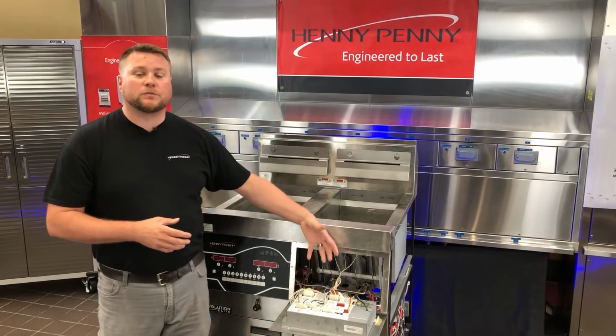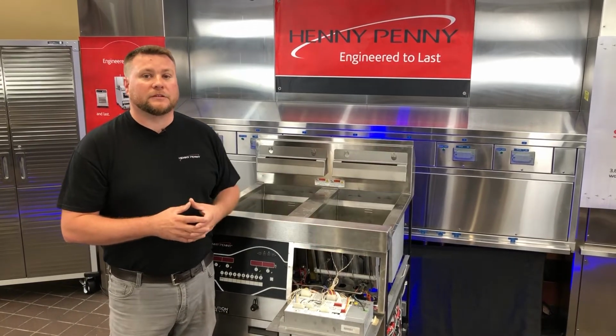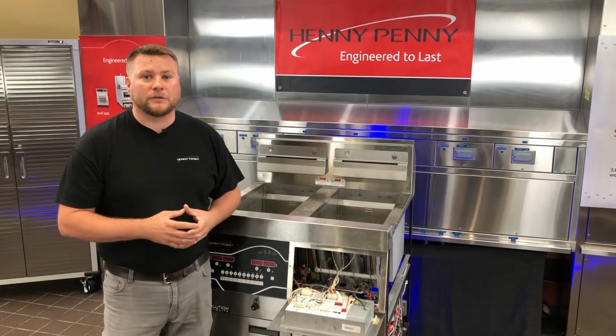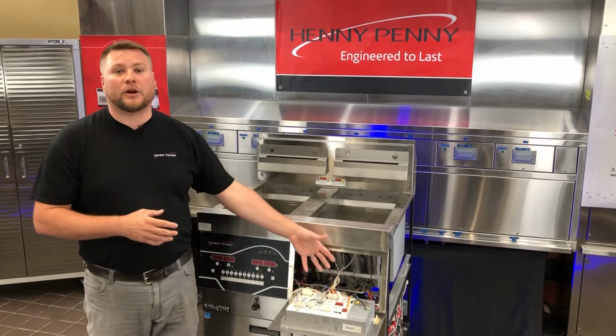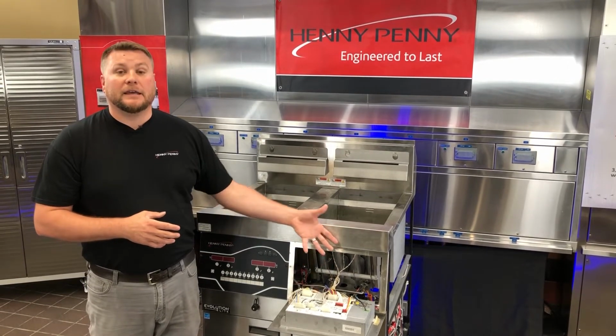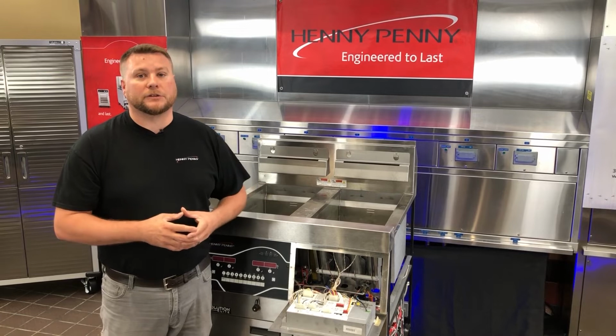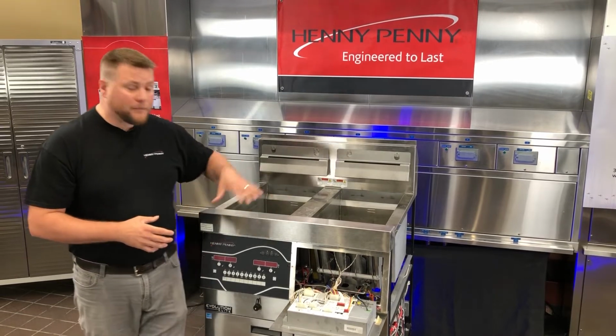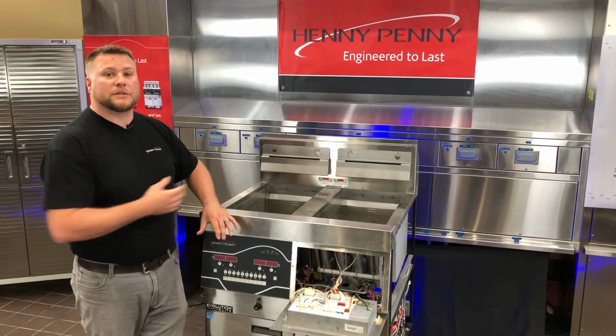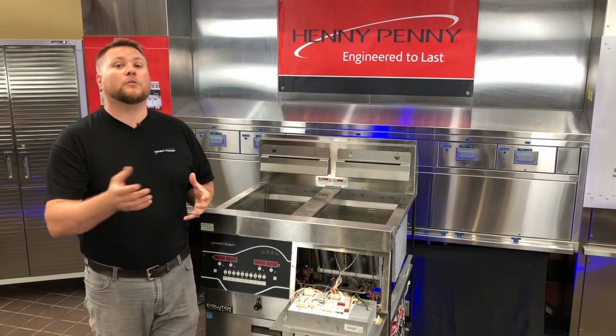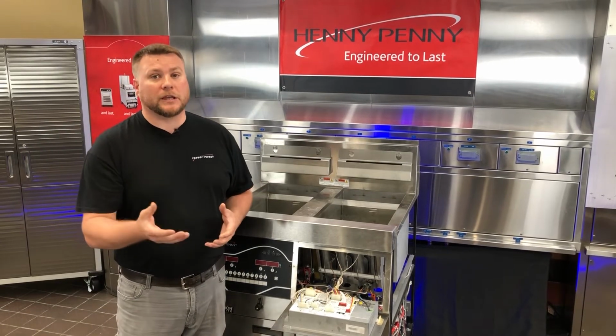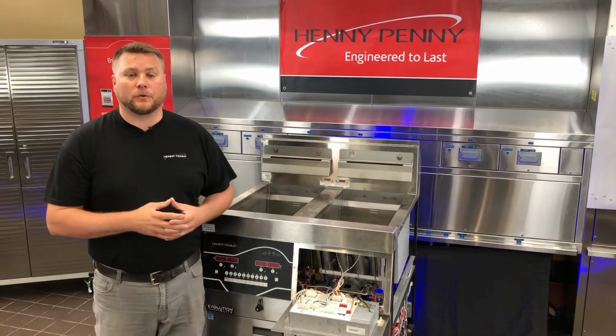After we've swapped our control panel over to this other side, we can power the unit back up and see if that problem followed that control panel. If it did, then we know we have a faulty control panel. If the problem stayed over here even after we swapped the control boards, then we know we have a potential issue with the communication cable or the AIF board.